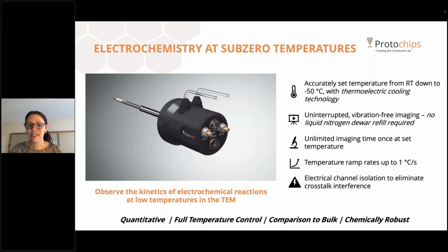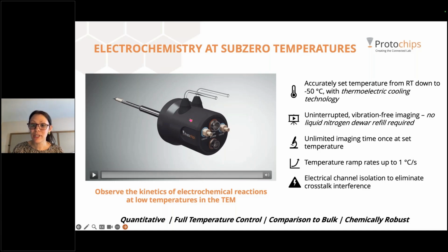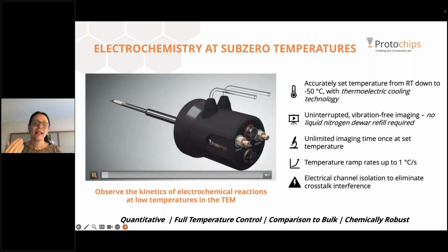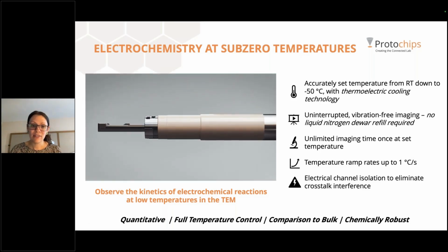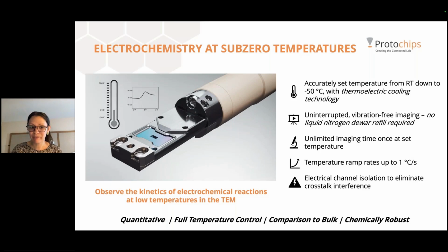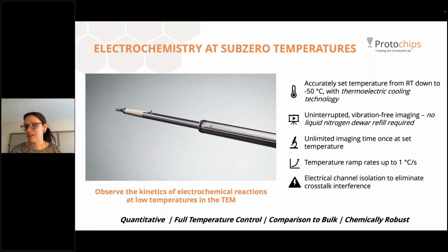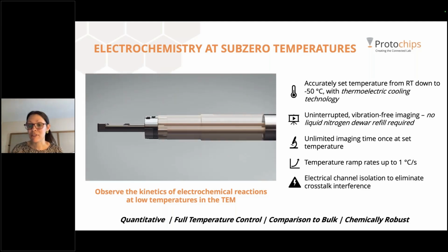Now, from the cooling aspect, we do cooling a little bit differently. This isn't a cryo holder, keep that in mind. We're not trying to freeze the liquid. We're trying to create cooler environments. And so we are using a Peltier device for cooling, a thermoelectric cooler built into the back of the holder. It's going to cool down to minus 50 degrees C, which is your limit, by cooling through the holder, and it cools down the entire tip of the holder. Now, you don't have to go to that minus 50 degrees C. You're not bottoming out like you would with cryo, where you usually have to go to the coldest temperature. You do have control over that temperature, and I'll show you how the cooling works together with the heating to do that modulation. But because we're not using liquid nitrogen, you don't have a dewar to refill, hence the unlimited, stable imaging as well.